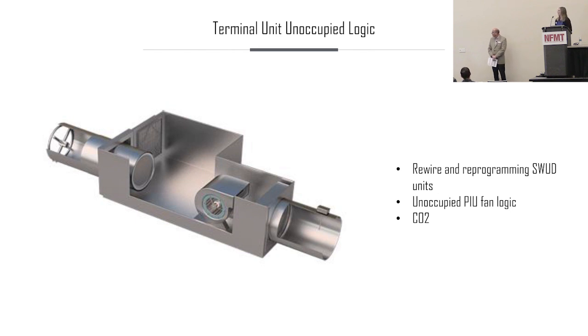Another way to potentially save some money on your TU logic, if you have PIUs or power induction units, basically VAVs, but they have a fan attached to them: in unoccupied mode, if that space needs heating, you don't necessarily have to bring on an air handler to go condition that space. You can just use that plenum air going through those PIUs, using that fan, using that heating coil or electric heat to reheat the space and not even have to ever bring on the air handler, which is only if they're in heating mode. But that's just another thing that in design, a lot of people don't program it that way just because they see a PIU as a VAV, but they are different types of units.